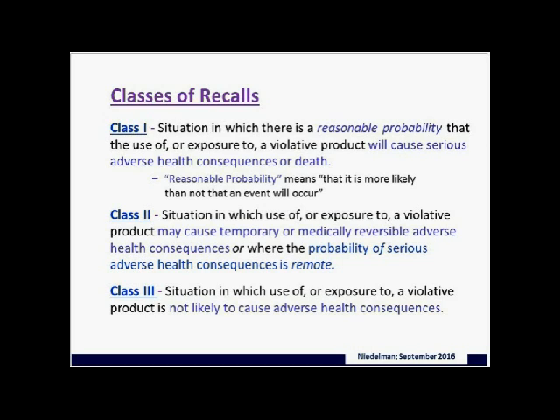That may be what it says in black and white, but it is not in practice what FDA follows. They look at the severity of a particular problem, and you will see there have been recalls with an N of 1, where one person died as a result of the use of the device, resulting in a Class 1 recall. And these are for devices that were out on the market for a considerable period of time. So don't place a lot of confidence in that reasonable probability definition.